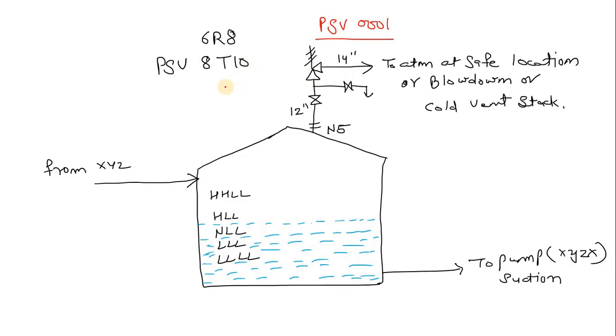For example, if the set pressure of this PSV is 6 kg per centimeter square gauge, then when the pressure within the tank achieves 6 kg/cm², the PSV will pop up and the fluid will relieve. When the pressure decreases below 6 kg/cm², the PSV will close down. I have already prepared videos about how the PSV works — you can watch those as well.